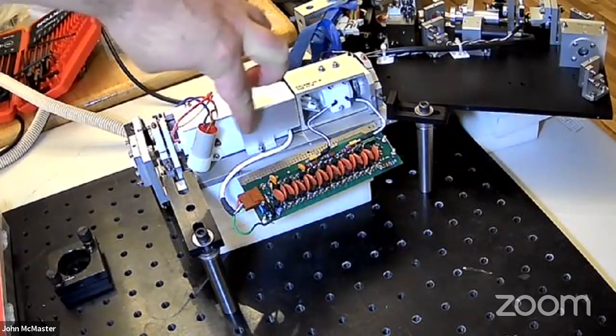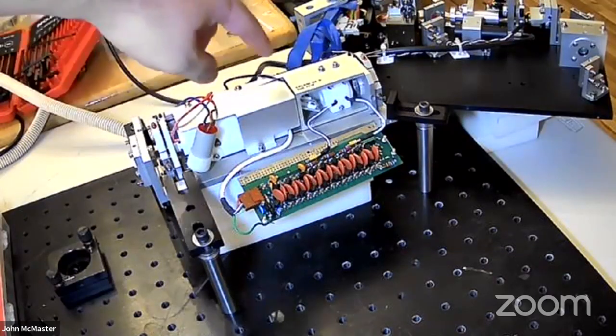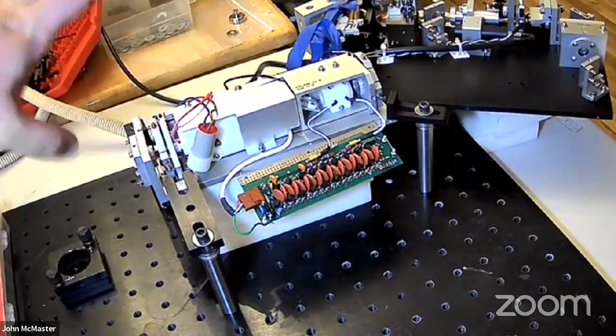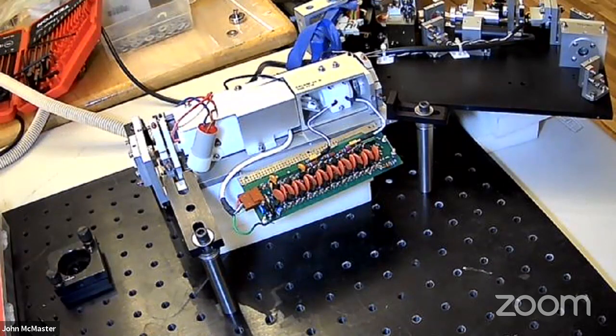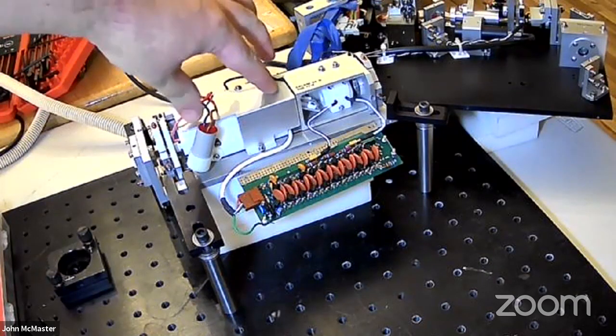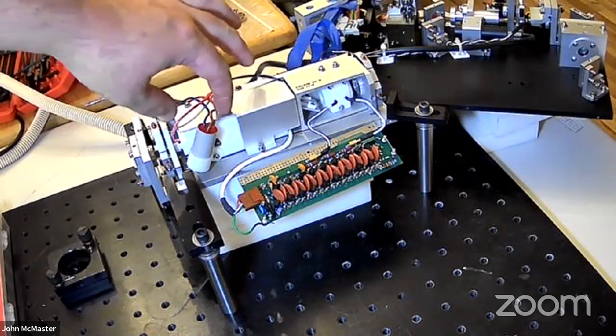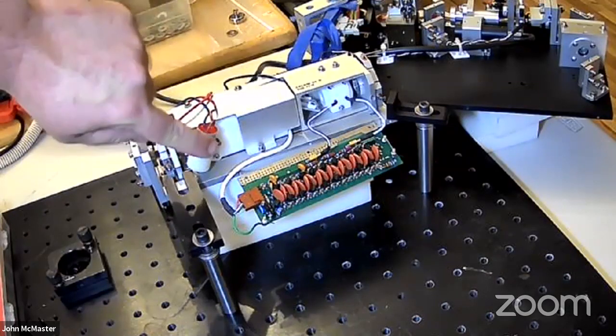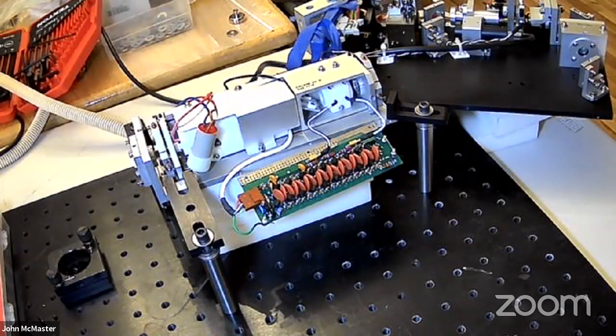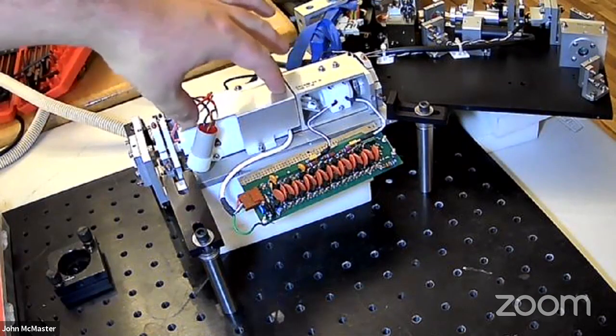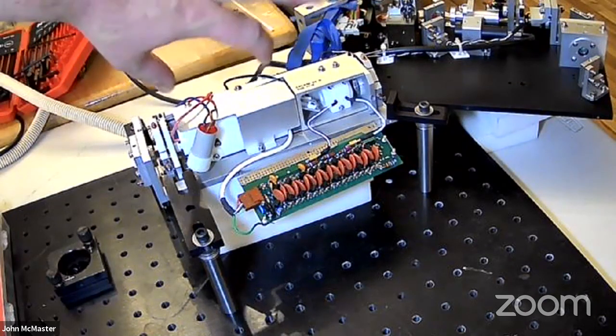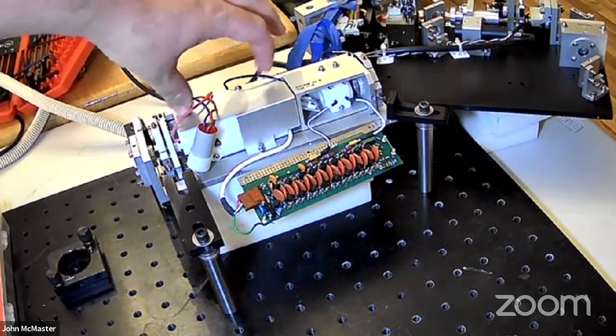There is actually a high power flash lamp in here. So that's what this red and this black is. A high voltage capacitor off screen stores a lot of energy and then dumps it into a glass flash lamp that's in there, just like a camera. And a high voltage pulse is applied to fire that lamp.